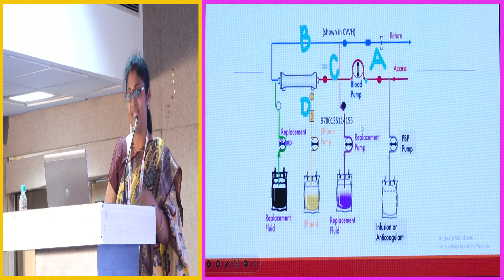So as I have discussed, A is the access pressure. I just want everybody to take this picture into your brains. The first one is the inflow or the access pressure. The access pressure is the negative pressure which is required to be generated to move the blood from the patient. Normal values are minus 50 to minus 200. So just remember, the first one is the access pressure, which is at the catheter of the patient, between the catheter and the blood pump. It is an indicator of a functioning vascular access.